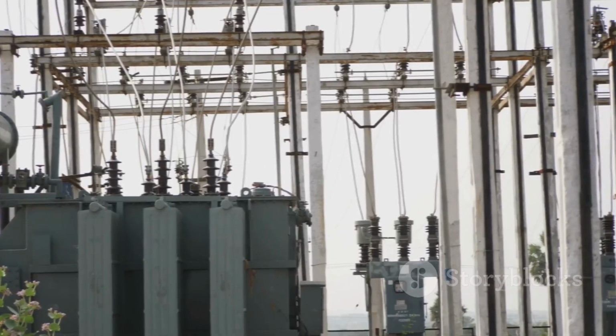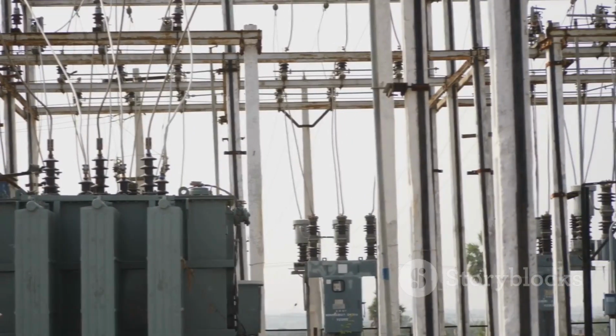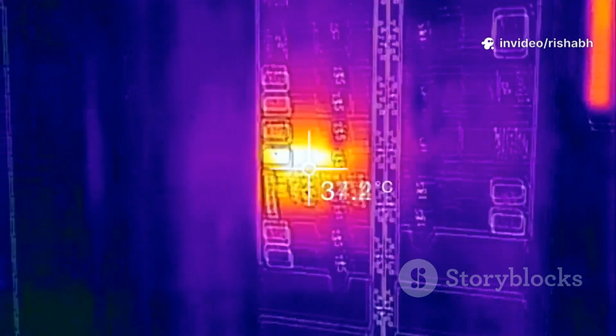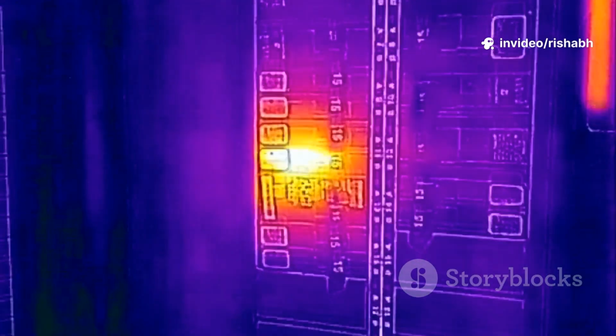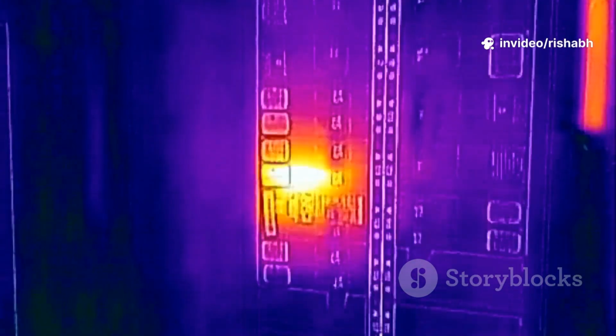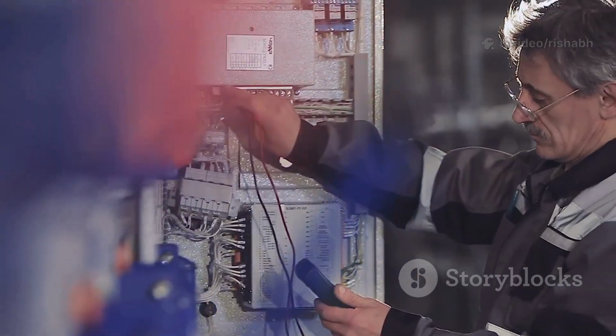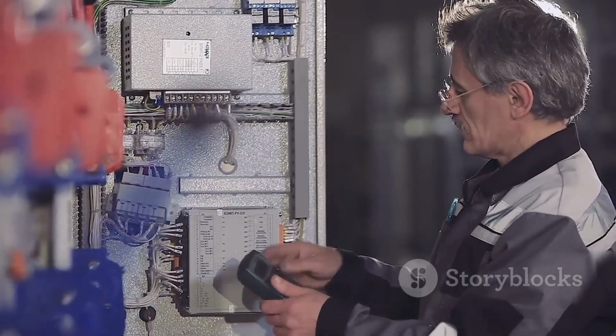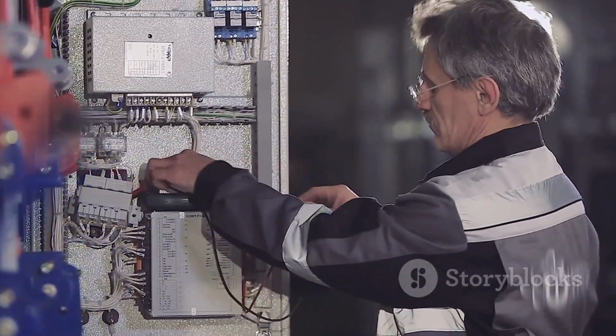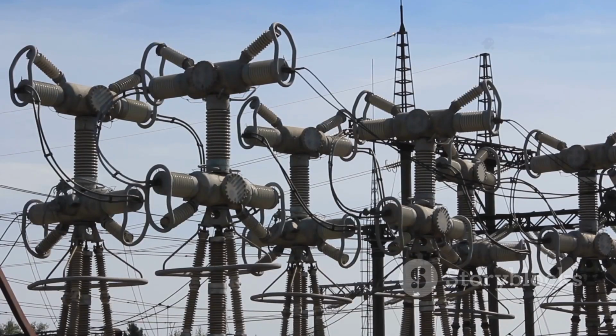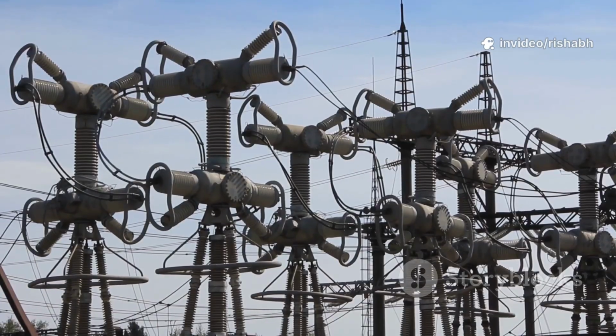The second crucial role of the oil is to act as a coolant. The core and windings of a transformer generate heat due to electrical losses. This heat must be removed to prevent the insulation from degrading and failing. The oil absorbs this heat from the hot windings and core.